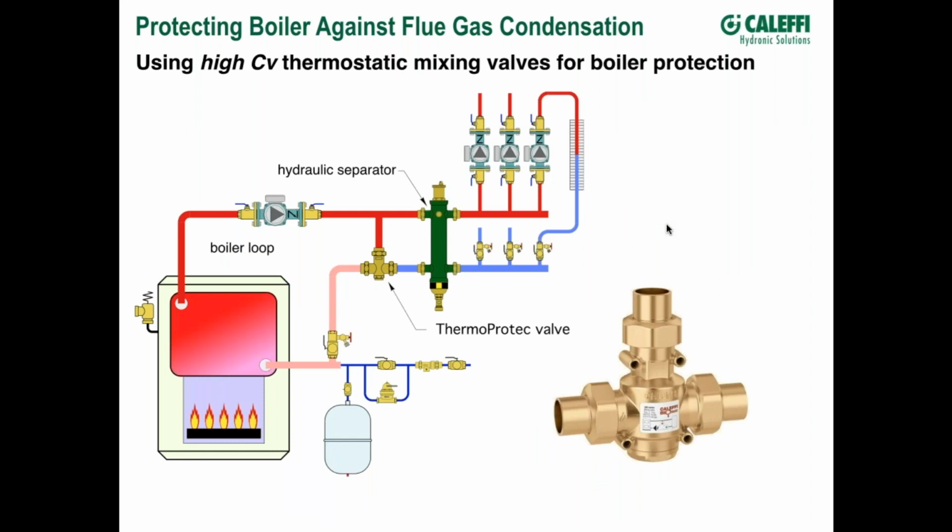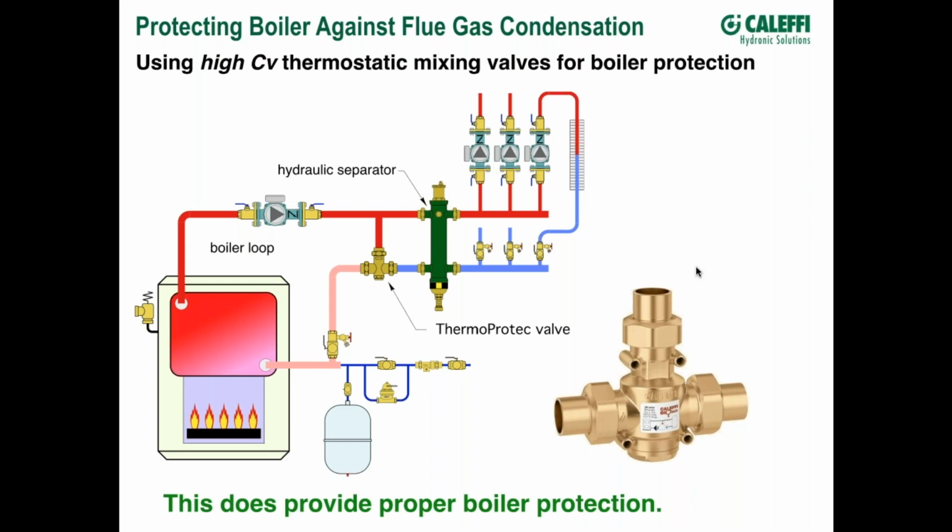So he had to put a little bypass line over to the boiler to fill it from the right side of the drawing. Yep. So when that valve's at room temperature, this what I'll call the cool port is completely closed. It closes tight enough that he couldn't get water across to fill the boiler, and he had a check valve up above, of course. So he probably had his fill coming in here versus down here. Exactly. He had it over on the distribution somewhere downstream there. But he was using one of our drawings.